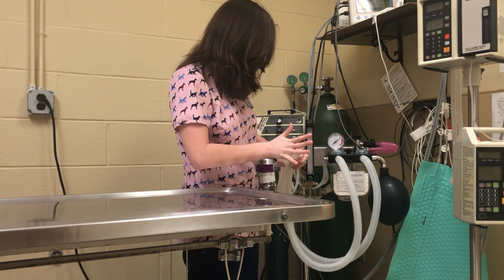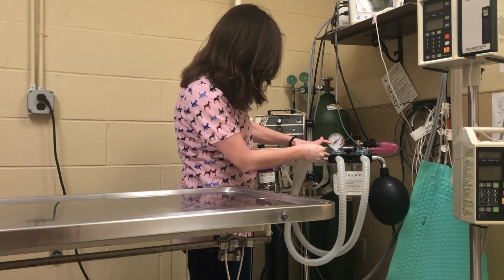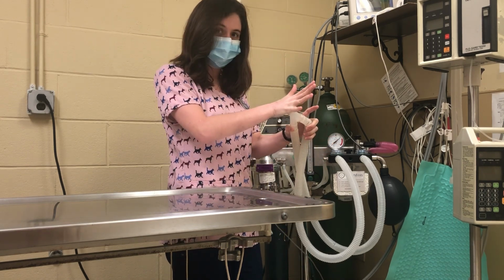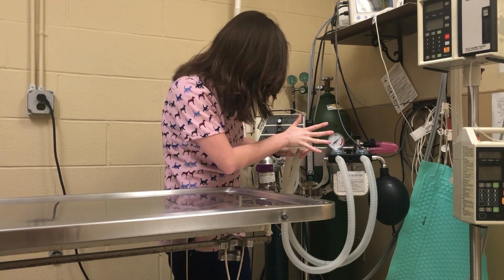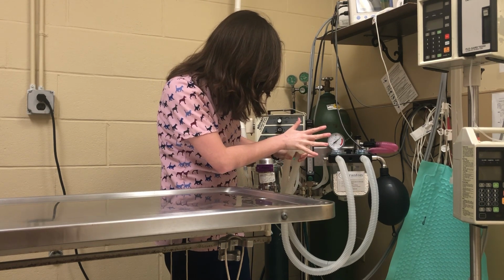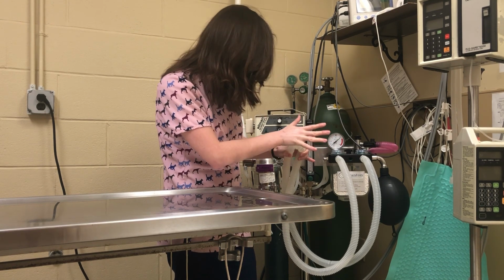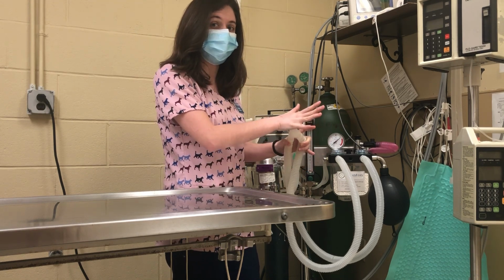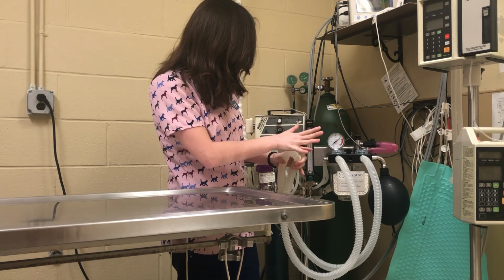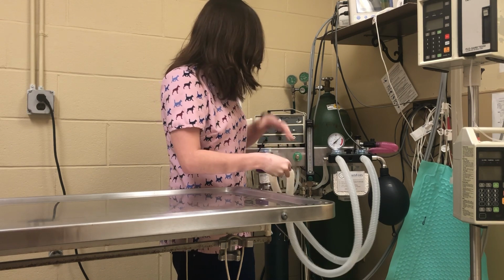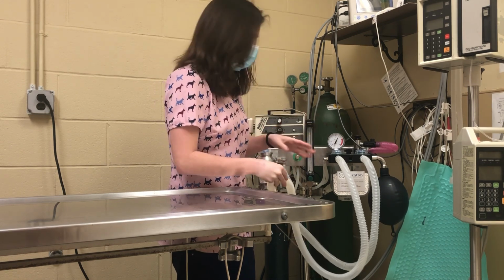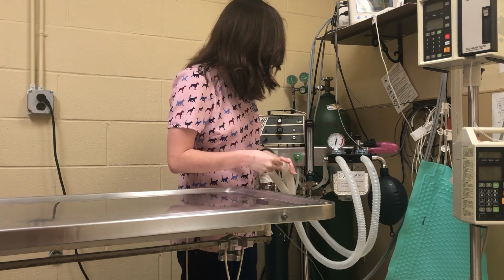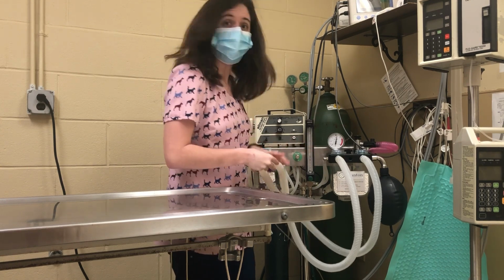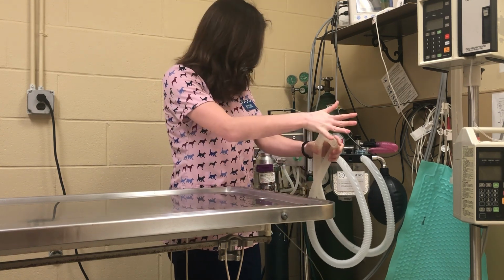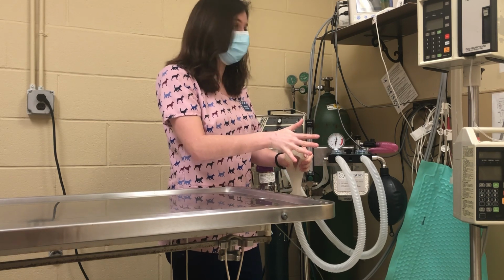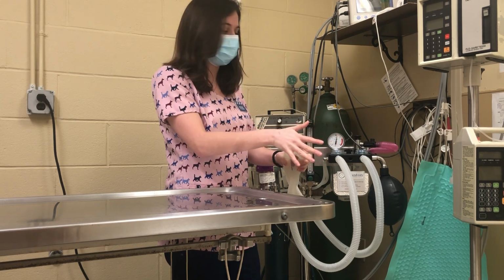about 20. So when we're looking at the manometer here, with it occluded like this, you can see that it's not moving from 20 centimeters of H2O. So that means that there is no leak. If there was a leak, then I would go about trying to find that, checking all of the tubing, checking the bag, making sure that everything is working the way it's supposed to be. But as you can see, this anesthesia machine is working just fine.